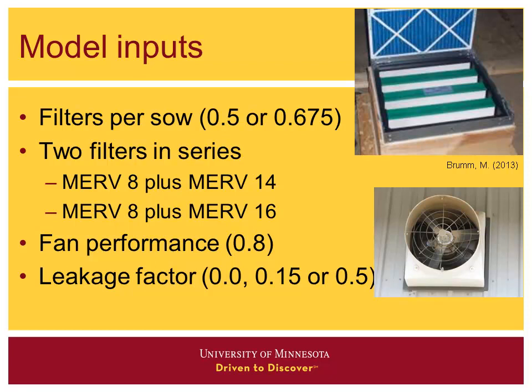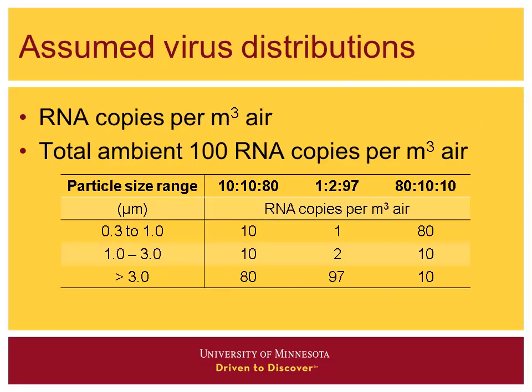I used a fan performance factor of 0.8, which accounts for the fact that fans don't perform quite as well as the best lab reports indicate — we've never found them to do quite as well in monitoring. The feedback we got from industry was that our leakage rate was pretty high, so we've been using just a fraction of it: 0.15 and 0.5.